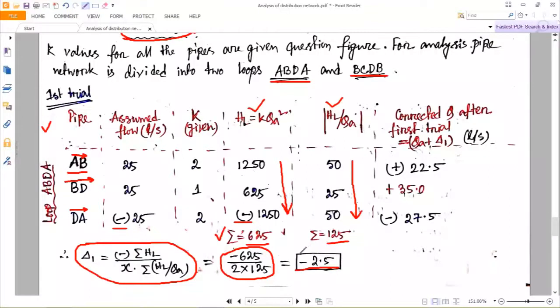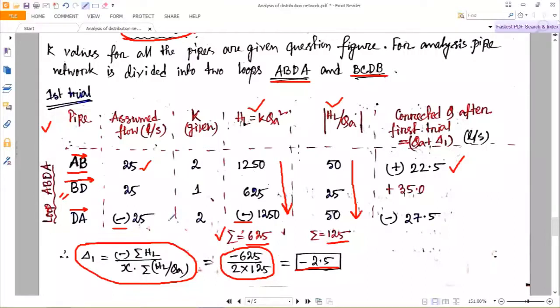Apply the correction Δ₁ = −2.5 to each pipe in loop 1. For pipe AB: assumed flow 25, apply −2.5, corrected flow = 22.5. For pipe DA: assumed flow −25, apply −2.5, corrected flow = −27.5. Leave pipe BD for now — it is a common pipe and we have to apply extra correction to it later. Calculate only pipes AB and DA at this stage.